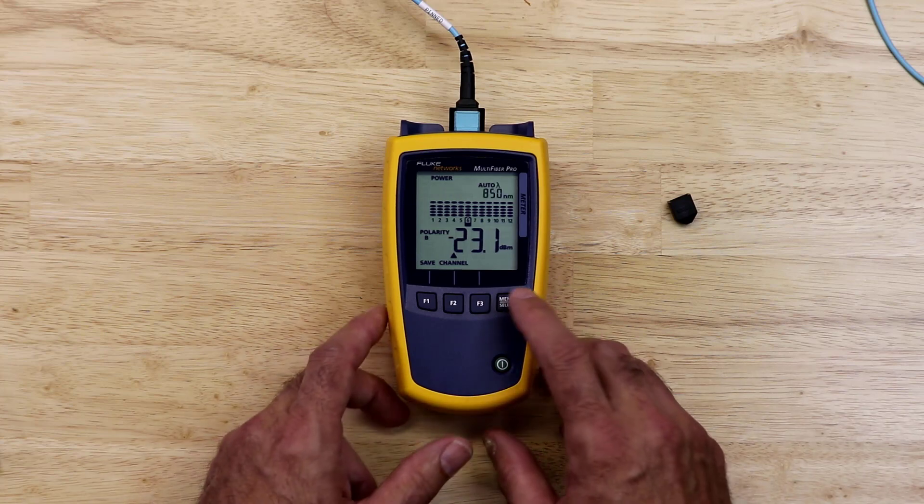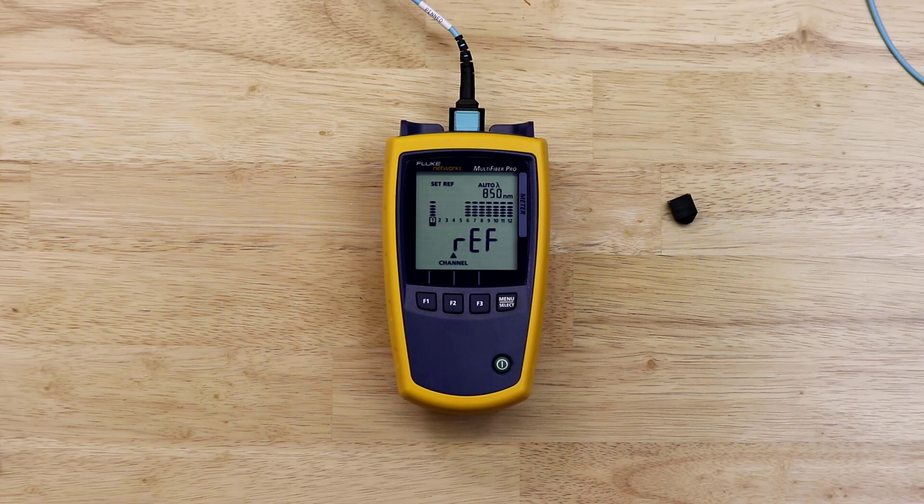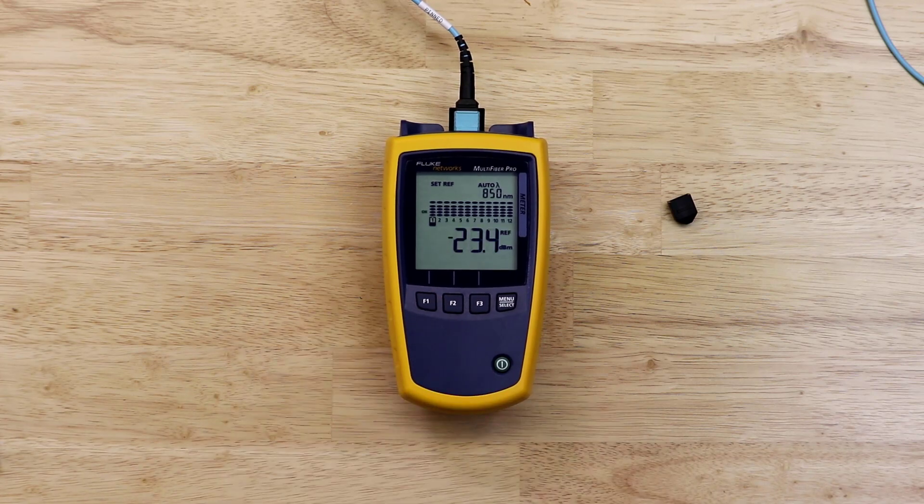To get to the set reference option, I will press menu select once. Referencing will begin automatically. After the meter has gone through all 12 channels, I will press save to set the reference. Once the reference has been set, the meter will switch to the loss screen. It is best to keep an eye on this screen for about 30 seconds.